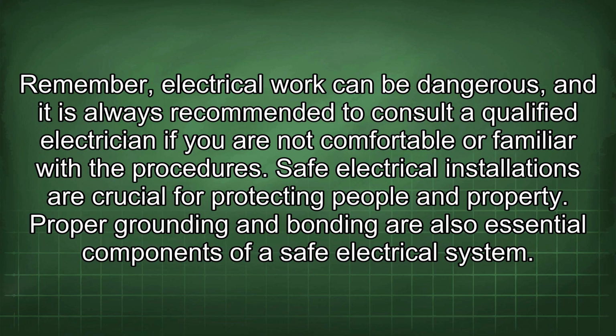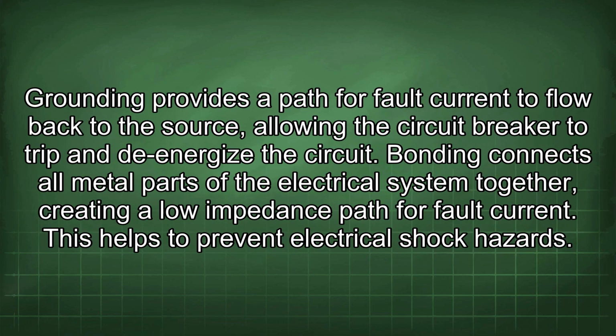Safe electrical installations are crucial for protecting people and property. Proper grounding and bonding are also essential components of a safe electrical system. Grounding provides a path for fault current to flow back to the source, allowing the circuit breaker to trip and de-energize the circuit. Bonding connects all metal parts of the electrical system together, creating a low impedance path for fault current. This helps to prevent electrical shock hazards.